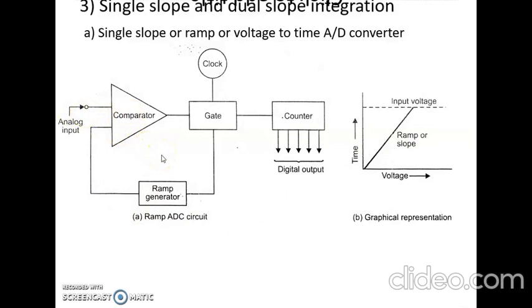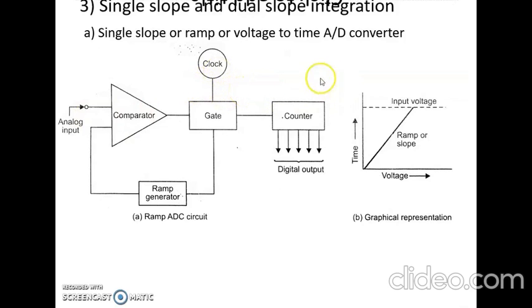The time consumed by the ramp voltage to increase to a value equal to the sensor voltage depends on the size of the sampled analog voltage. When the ramp voltage starts, a gate opens and a binary counter begins counting regular pulses from the clock. When the ramp voltage equals the analog input voltage, the gate closes and the count indicated by the counter is the digital representation of the sampled analog voltage.